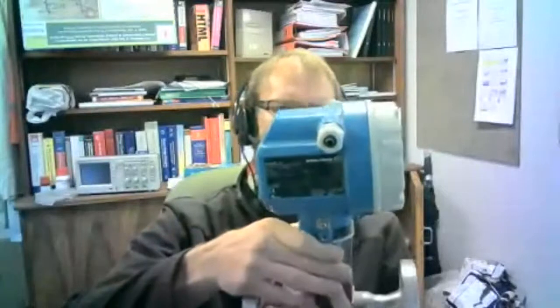Vortex shedding flow meter. And this device here is obviously connected to some power supply, and it sends out a signal to our control system. That signal is in this case a 4 to 20 milliamp signal. So it's a current that varies as the flow rate varies within the range.